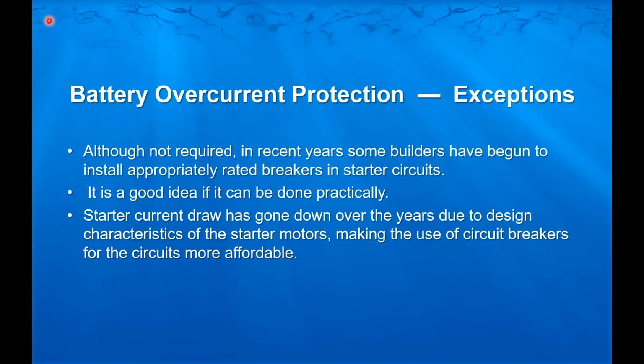We'll talk a little bit later about battery switches and inrush current as far as ratings, and they'll survive an inrush current, but a fuse is a fuse. Depending on its personality, a breaker is going to trip on that inrush current and never give you a chance. So if you've got a starter that has a low enough draw and you can put a proper size breaker in there that doesn't cost $1,000, you're probably right in wanting to do that.